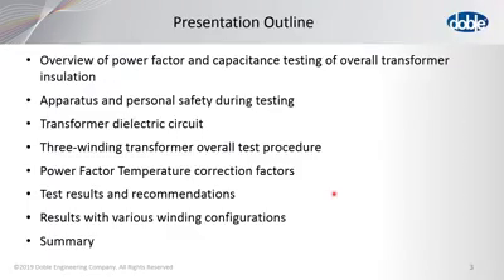The presentation will follow this outline. There'll be an overview of the power factor and capacitance testing. There'll be a section on apparatus and personnel safety, because that's very important to any testing regimen. The transformer dielectric circuit for the three-winding transformer will be explained. And then there will be overall test procedures given for both the M4100 and the M7100, which are the two most premier Doble testing equipment now available. There will also be a section on power factor temperature correction factors. Then we'll go into how the test results are analyzed and the recommendations. Various winding configurations will give some unusual results, which will be explained. And then a summary will be given on the whole presentation.